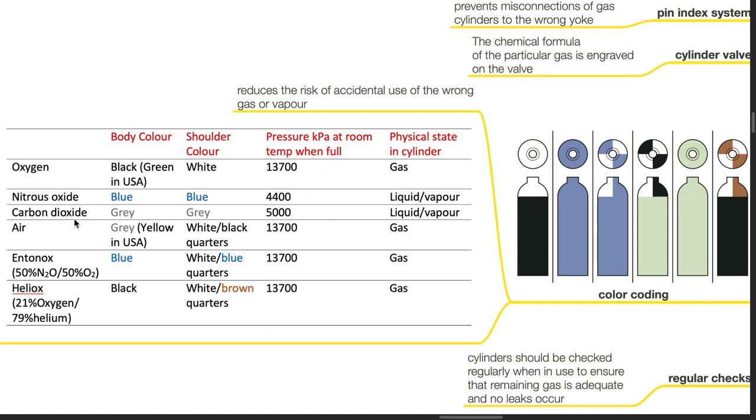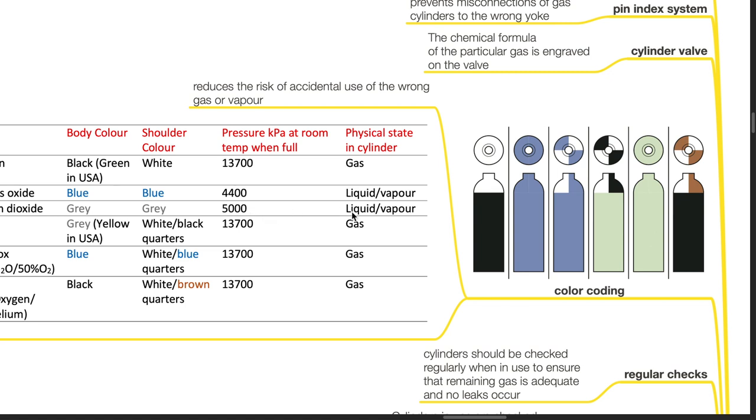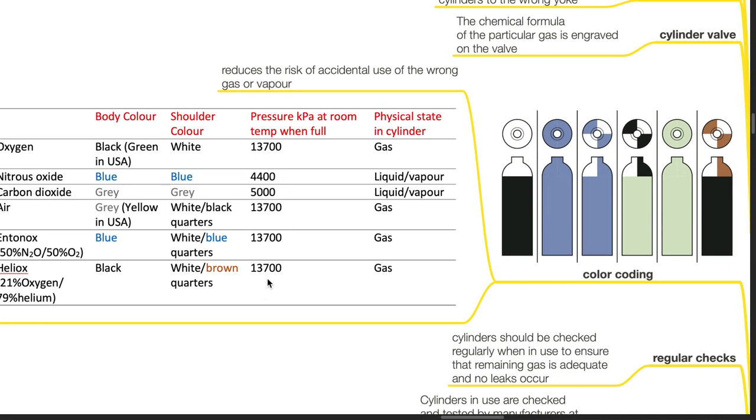Carbon dioxide gas cylinders has a grey body colour and grey shoulder colour. Pressure at room temperature when full is 5,000 kPa. Physical state in the cylinder is liquid or vapour. For air, the body colour is grey, shoulder colour is white and black quarters. Pressure is 13,700 kPa at room temperature when full. Physical state in the cylinder is gas. For entonox, body colour is blue, shoulder colour is white and blue quarters. Pressure is 13,700 kPa at room temperature when full. Physical state in the cylinder is gas. For heliox, body colour is black, shoulder colour is white or brown quarters. Pressure is 13,700 kPa at room temperature when full. Physical state in the cylinder is gas.